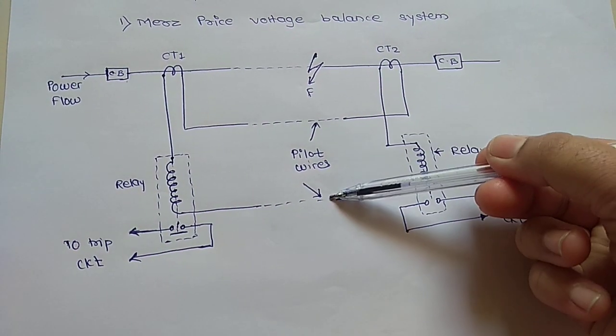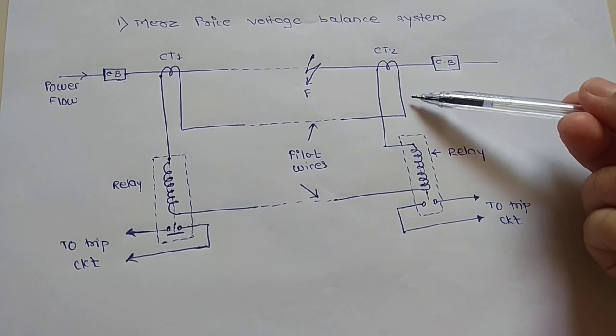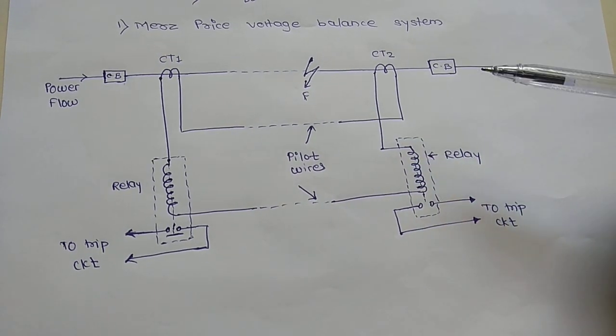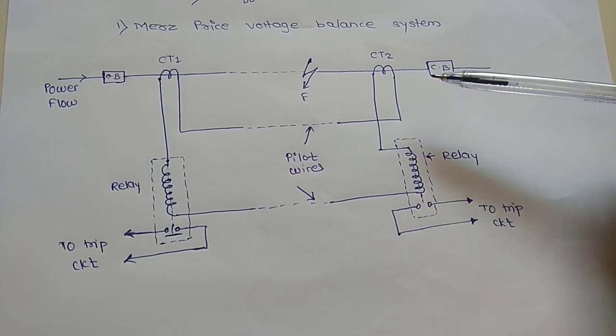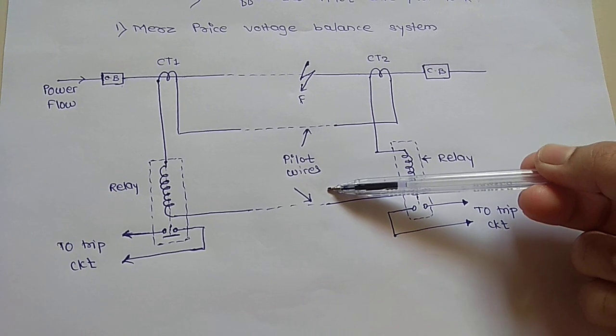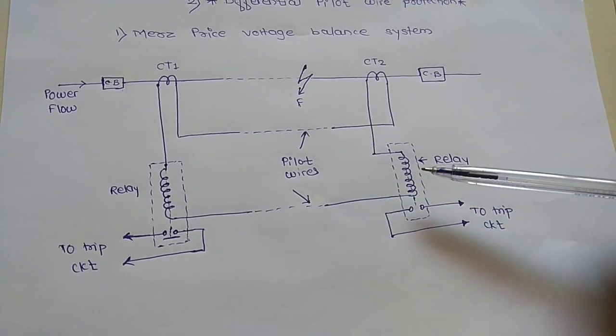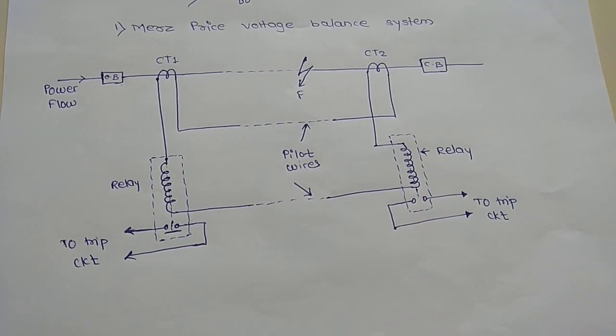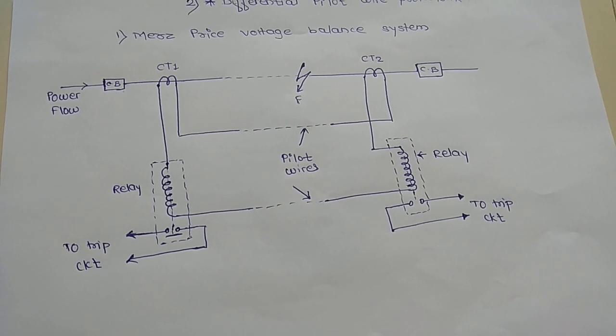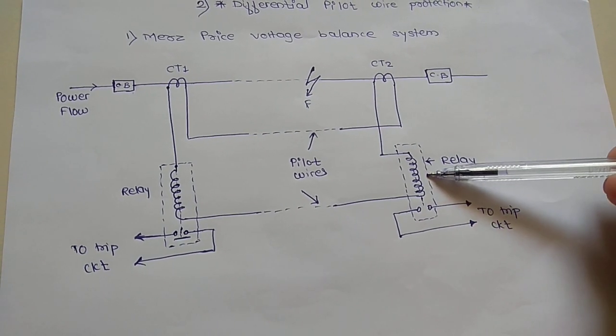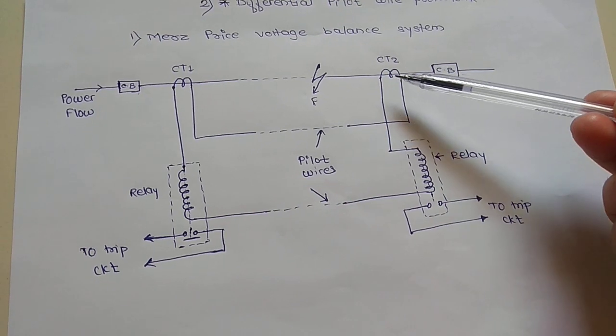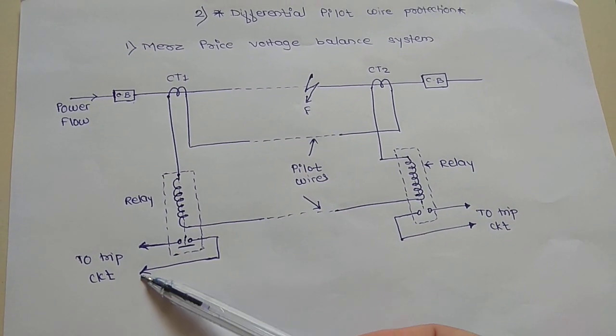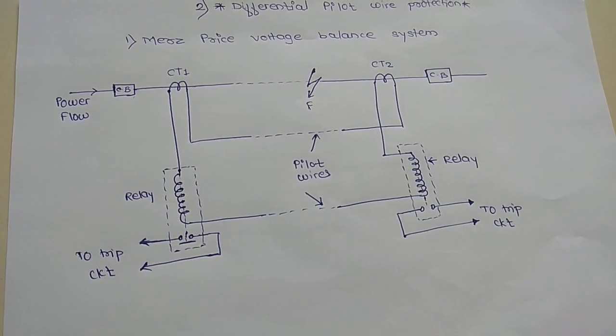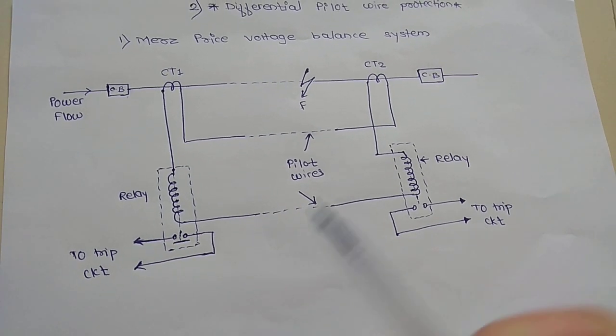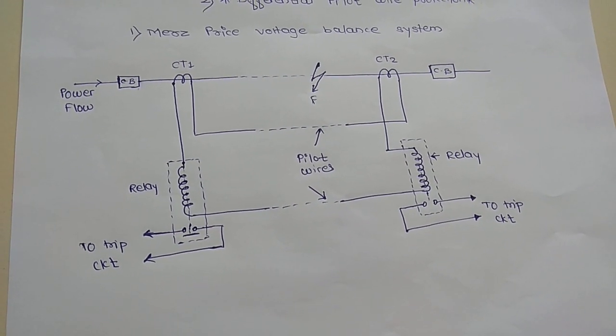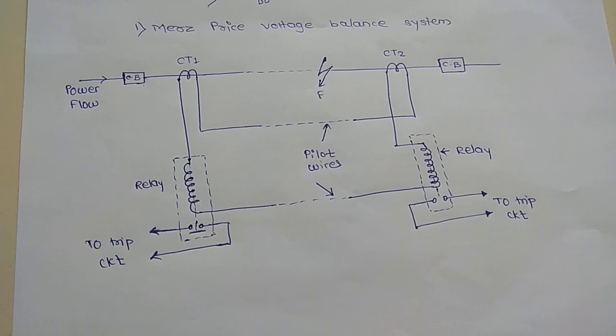The pilot wire connects the two CTs, and therefore unequal voltages cause current to flow through this pilot wire as well as through the two relays. Due to this, the circuit breakers at both ends will trip out, isolating the fault on the line.